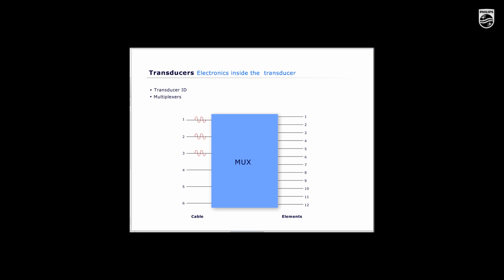Inside the transducer are some electronics, one of which is the transducer ID. This contains the identification process to identify to the ultrasound what kind of probe is being connected. Additionally, if the number of elements inside the transducer exceeds the number of wires available or connections, multiplexing is used to route the signals. Multiplexing is a method used to reduce the number of channels used in the cable of the transducer. One wire is used for signals from different elements, and they are timed in the appropriate sequence to send to the ultrasound system.